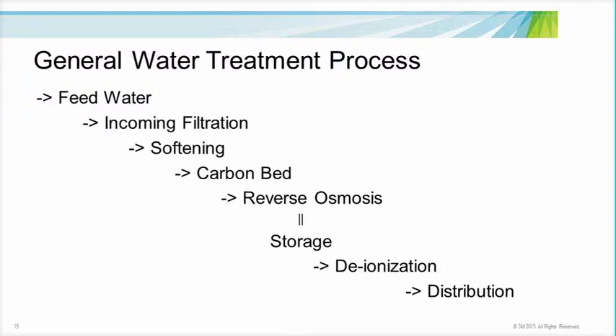Once the chlorine is removed, the system becomes extremely susceptible to microbial propagation and growth, commonly referred to as biofilms. This is the main point and the main control issue in many of our high purity water systems or high quality water systems. In this scenario, the principal treatment method is reverse osmosis. Due to the fact RO membrane filtration is a slow process, a storage tank is required to meet peak demands from water usage. After storage and prior to distribution, the water is deionized.